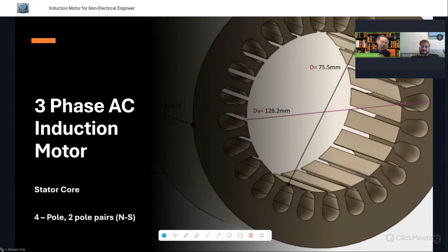That will be unbearable to the motor. So normally we start the motors with the valve closed. Now, if you want a higher starting torque, then you have to go to a direct online method, where the full voltage is available at the motors and it will start off with high torque. But that is more on the control side. For the motors, we will see how the torque is produced, the relationship between torque and voltage, and how the VFD controls the flow or the operating point of the motors. I hope that answers the question.